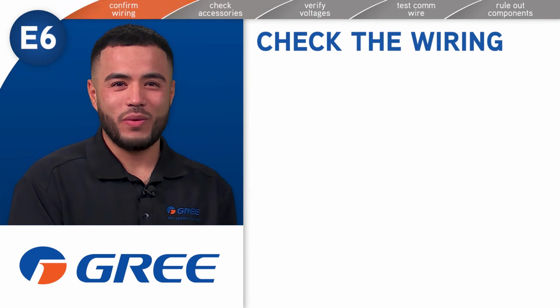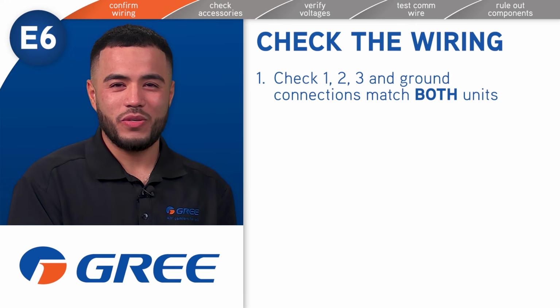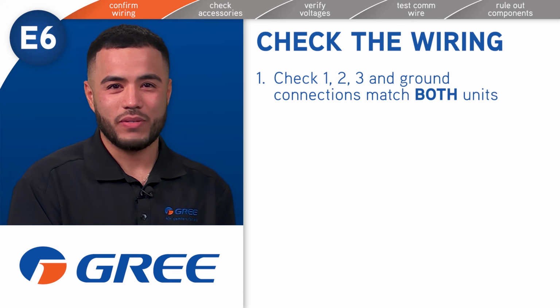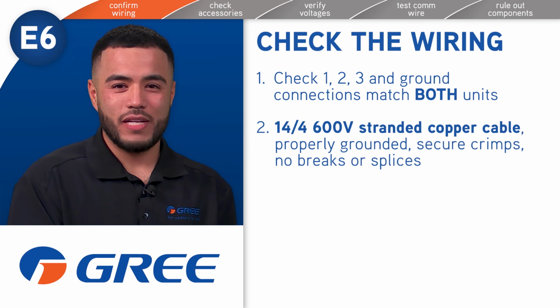First, check the wiring. Make sure the 1, 2, 3, and ground connections match indoors as well as outdoors. Confirm the cable is 14-4 600 volt stranded copper, properly grounded and with good crimp connections. Ensure there are no breaks or splices.